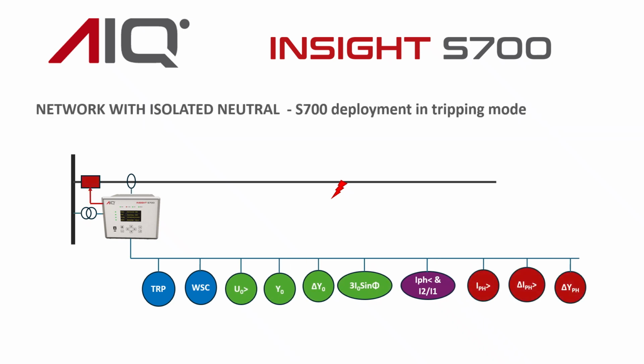If S700 is deployed for operating the circuit breaker, phase fault detection algorithms including phase overcurrent, delta overcurrent and delta admittance can all be applied to operate the circuit breaker for phase faults. Systems with isolated neutral allow transient earth faults to be self-extinguished. Tripping can be arranged for permanent earth faults. Lastly, auto reclose scheme is available to restore power after tripping if the fault is found to be transient in nature.